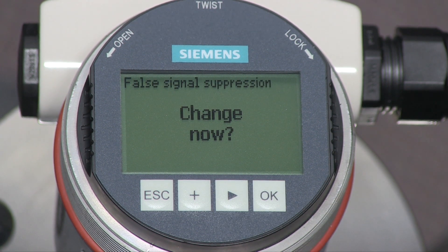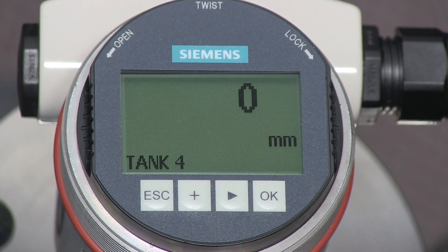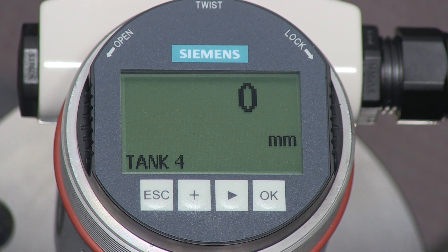The last parameter in the quick setup is the false signal suppression. This is used if the tank contains any obstructions that may affect the level value. If there are obstructions, lower the liquid level in your tank below the end of the rod and then turn on this parameter. Our tank does not have any obstructions, so we will leave this parameter set to the factory default. The Sitrans LG250 is now configured for our application.